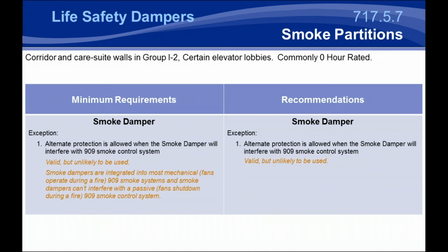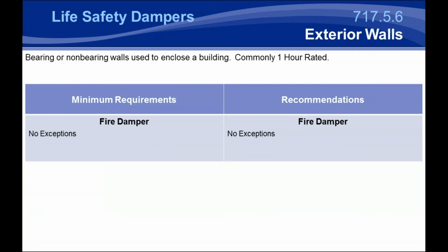Some smoke partitions that are more commonly 0 hour rated, but can be 1 hour rated, are used in corridor and care suite walls in Group I2 occupancies and certain elevator lobbies. And because these are smoke partitions, basically the only exception is to remove a smoke damper that will interfere with a 909 smoke control system, which we've said a few times is very unlikely because they're tied back into that smoke control system. Now, exterior walls are a little bit different.